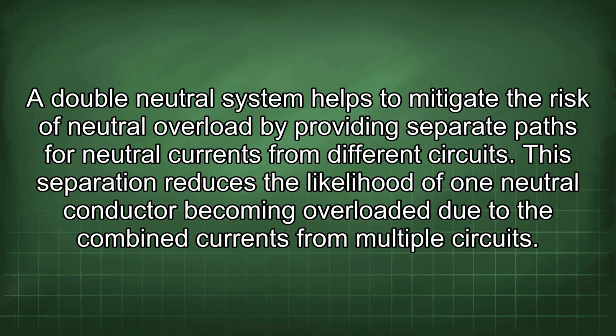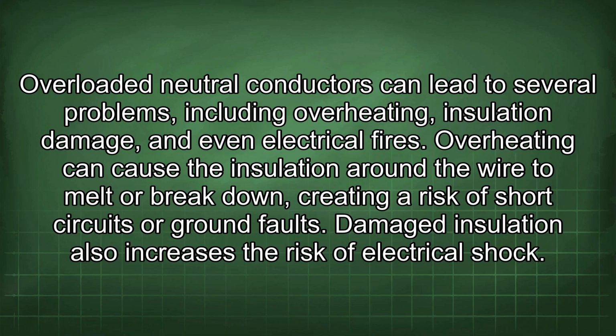A double neutral system helps to mitigate the risk of neutral overload by providing separate paths for neutral currents from different circuits. This separation reduces the likelihood of one neutral conductor becoming overloaded due to the combined currents from multiple circuits. Overloaded neutral conductors can lead to several problems, including overheating, insulation damage, and even electrical fires.